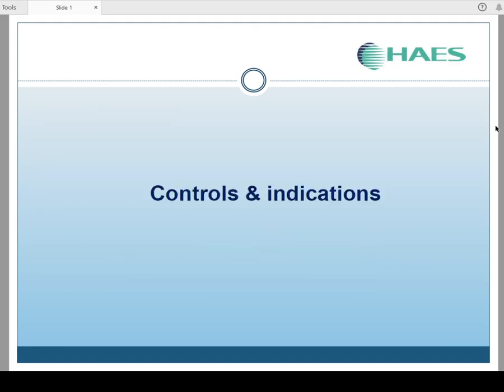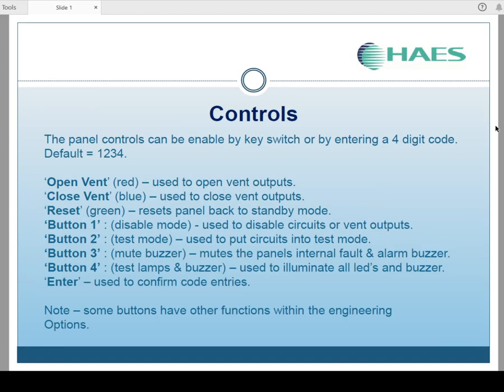Controls and indications. So the panel controls can be enabled by the key switch on the front or by entering a 4-digit code. The default is 1234, but this can be changed by the engineer. The controls you have on the front, you have an open vent control, which is in red. This is used to open the vents, obviously. You have then a close vent button, which is blue, used to close the vents. You have a green reset button, which resets the panel back to standby mode after an activation.